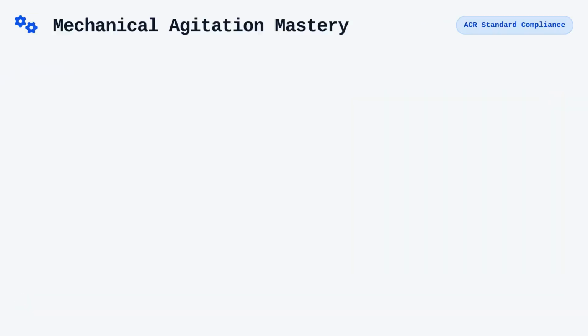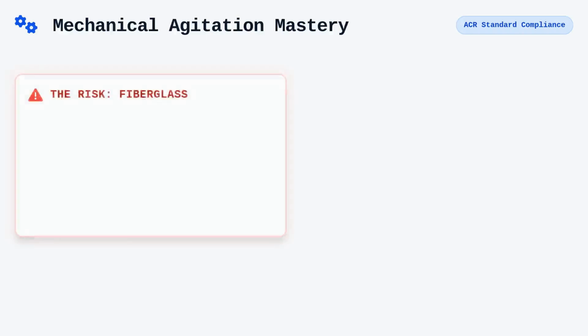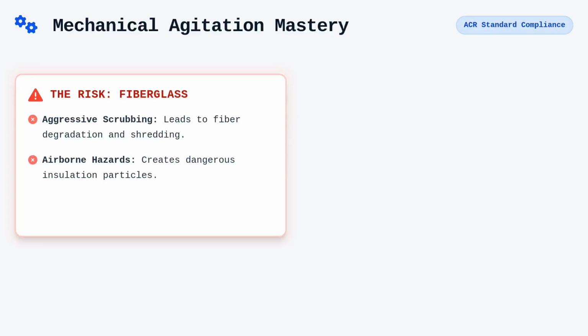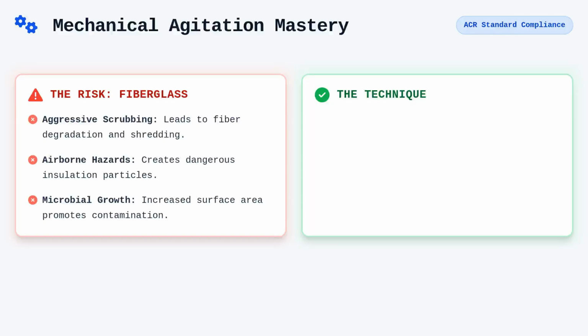Mechanical agitation requires a high degree of nuance, particularly when interacting with fiberglass-lined ducting. Unlike bare galvanized steel, fiberglass insulation is composed of bound fibers that can easily degrade if subjected to overly aggressive scrubbing or high-pressure agitation. If you shred these fibers, you create a potential for airborne insulation particles and increase the surface area available for future microbial growth, which is exactly what we aim to prevent. When navigating lined ducts, always opt for softer dusting brushes and maintain gentle, consistent passes that remove the debris without disturbing the underlying board material.